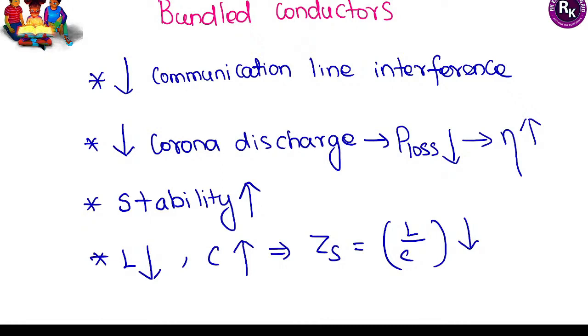Bundled conductors have many advantages and are often asked in examinations. Using bundled conductors reduces communication line interference and avoids corona discharge problems that arise with high voltage. Reducing corona discharge decreases transmission line losses and increases efficiency. Bundled conductors also increase stability, decrease inductance, and increase capacitance, which leads to a decrease in surge impedance.